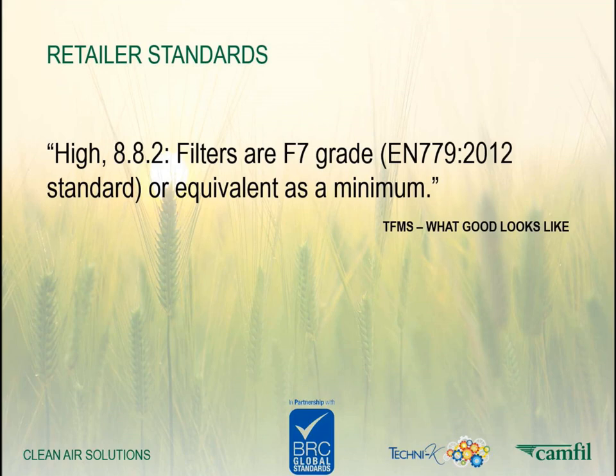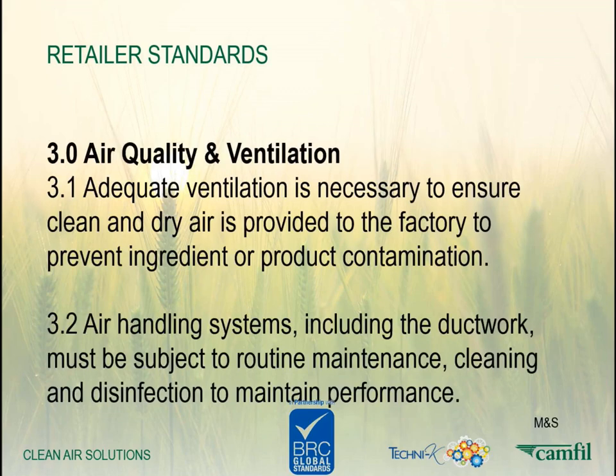The next clause in the Tesco standard talks mainly about positive air pressure, but it also goes on to say that in the what good looks like section, we need to use an F7 grade filter or equivalent as a very minimum. However, F7 on its own isn't sufficient, and I'll explain why later.